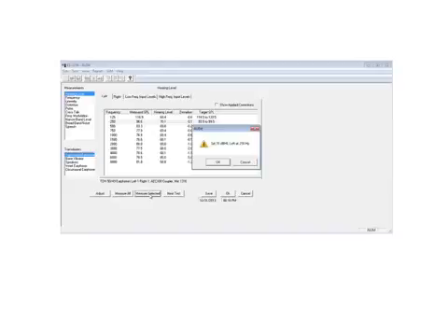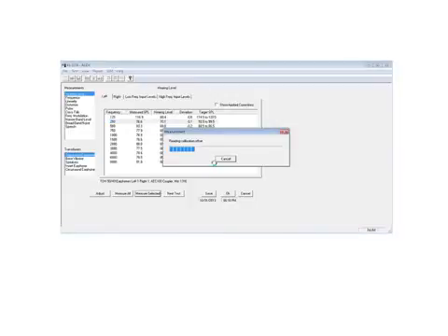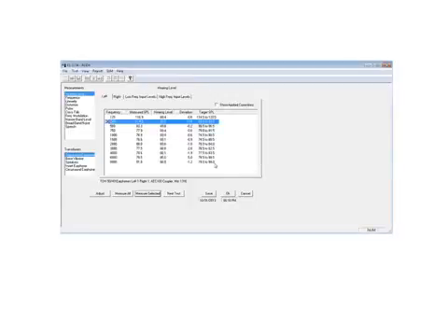What I'd like to do for the demonstration is just leave the calibrator on over the microphone, which we know is supposed to be 114 dB sound pressure level. And we'll tell this OK and measure my calibrator, which is over the microphone at this point in time.